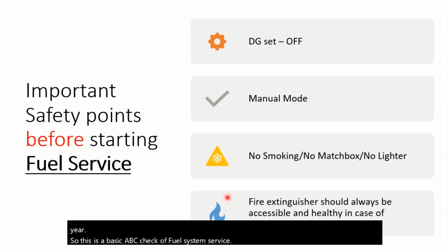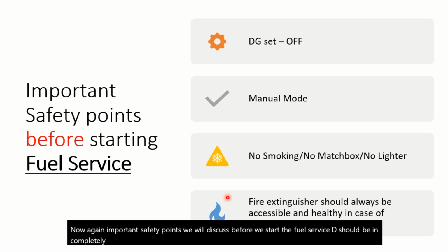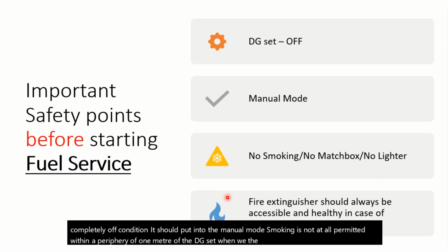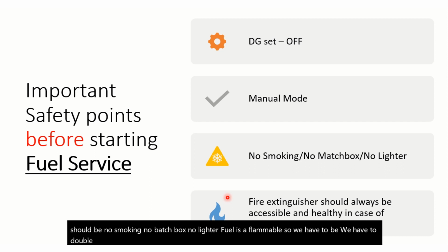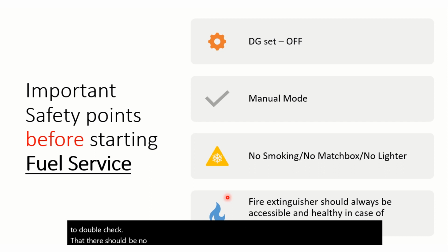Now again, important safety points we will discuss before we start the fuel service. The DG should be in completely off condition, and it should be put into manual mode. Smoking is not at all permitted within a periphery of 1 meter of the DG set. When the maintenance is carried out, there should be no smoking, no matchbox, no lighter.